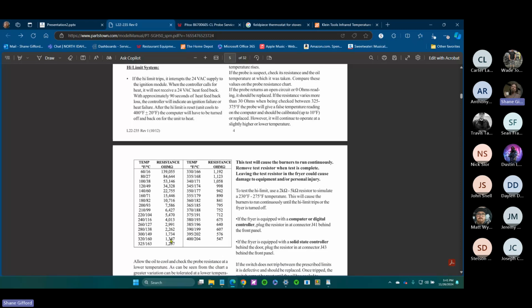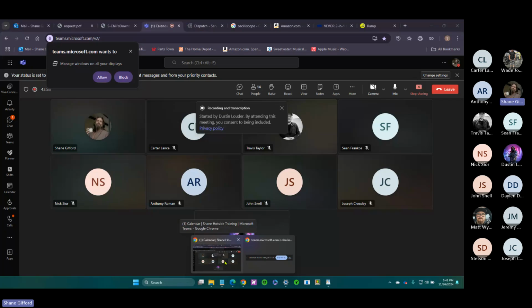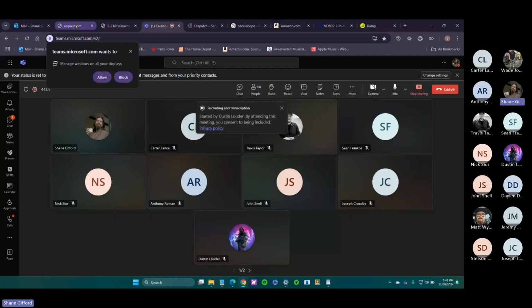The other scenario is that you actually are up to 350, 375, and you're reading high ohms, meaning the fryer thinks you're only at 150 degrees, but in reality, you're way hotter than that. Very, very important thing, because where did it go? Sorry, I lost my pages.